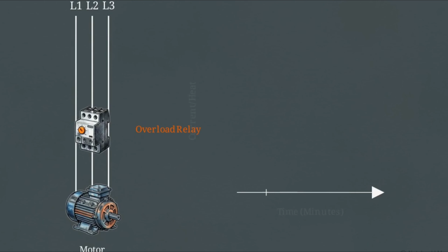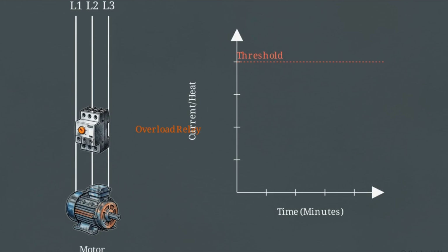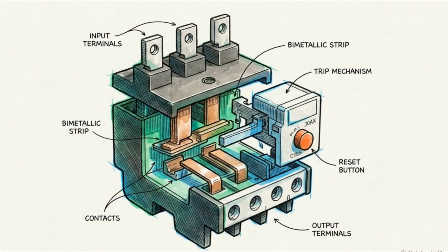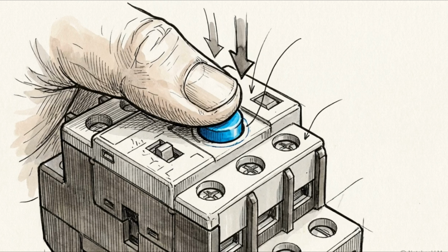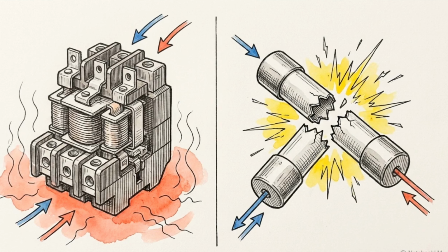This relay continuously monitors the thermal increase of the circuit. While the motor glows increasingly red, the graph on the right tracks the slow upward trajectory of the electrical draw. Once that slow climb crosses a specific threshold, the relay recognizes the jam and trips, opening the circuit and cutting power. Unlike a fuse, an overload relay does not destroy itself. Once the mechanical jam is cleared and the internal mechanism cools down, the operator simply resets the device. This completes our bifurcated defense. The overload relay provides slow, sustained thermal protection, while the fuses stand guard against sudden catastrophes.